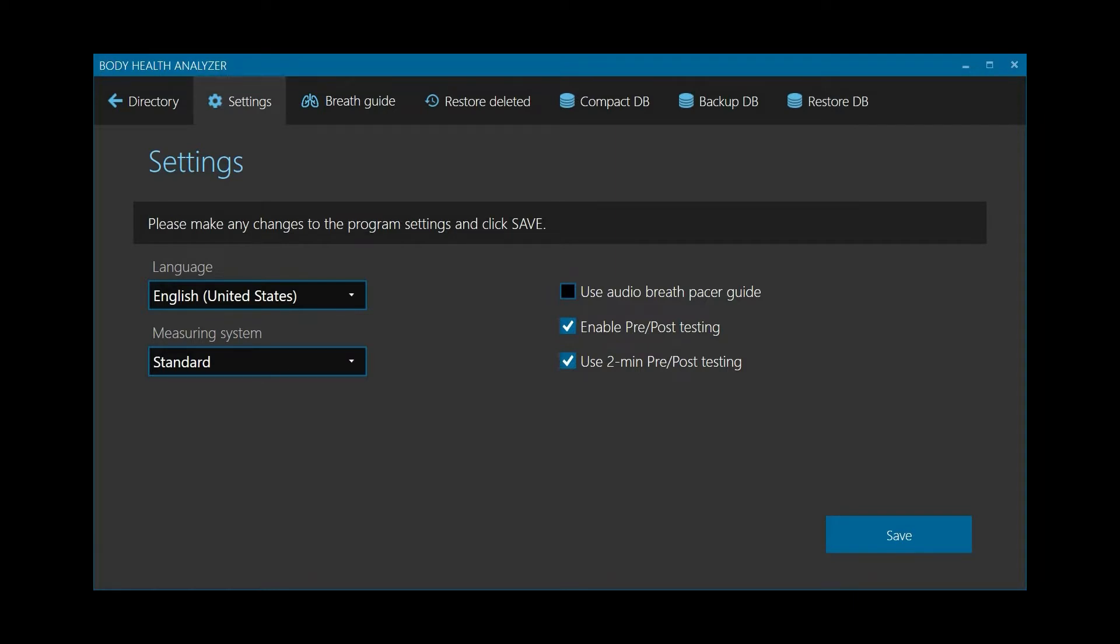If your testing schedule is really tight, set Use 2-minute pre-post-testing. This will save a few minutes on each testing procedure. However, some restrictions on obtaining specific test results will take place because certain metrics require a minimum of 5 minutes of recording to be estimated.